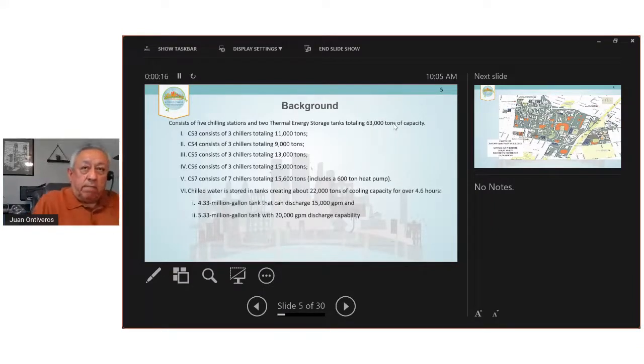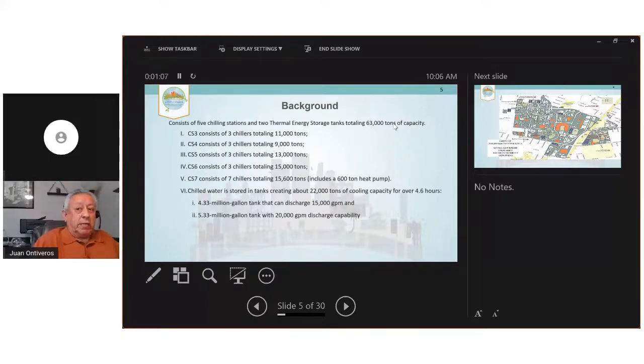Our system consists of 5 chilling stations and 2 thermal storage tanks. The chilling stations are 63,000 tons, and we have about 10 million gallons of thermal storage. Chilling station 3 is 3 chillers, totaling 11,000 tons. Chilling station 4 is 3 chillers with 9,000 tons. Chilling station 5 is 3 chillers, totaling 13,000 tons. Chilling station 6 is 3 chillers, totaling 15,000 tons. And 7 is 7 chillers, totaling 15,000 tons, plus a 600-ton heat pump chiller. The heat pump chiller is primarily designed to provide hot water to a medical district. Chill water is stored in 2 tanks. That gives us 22,000 tons.